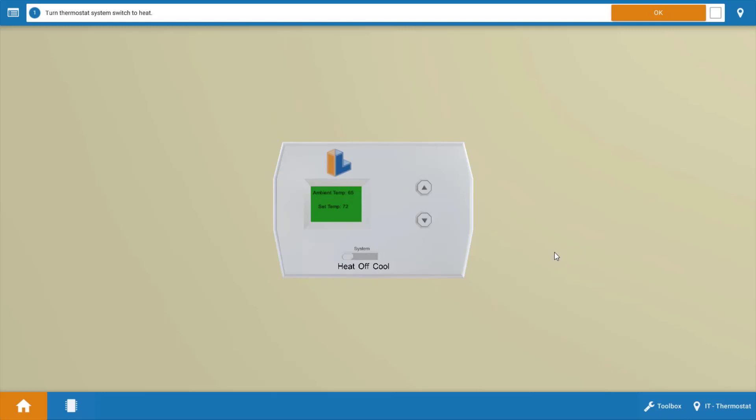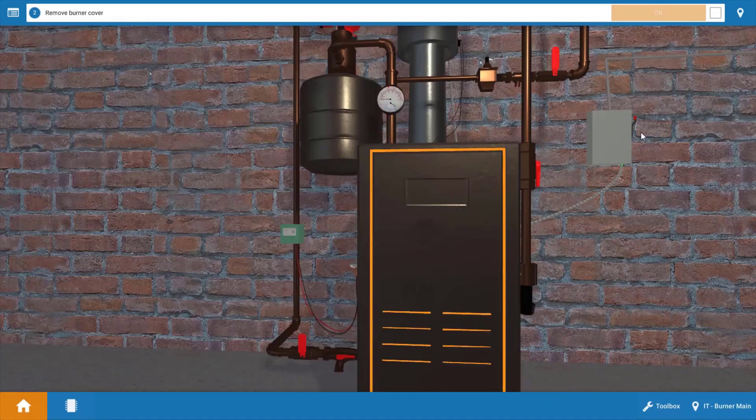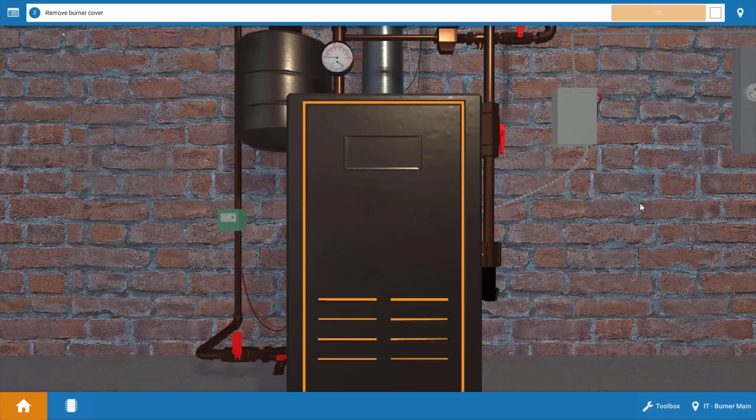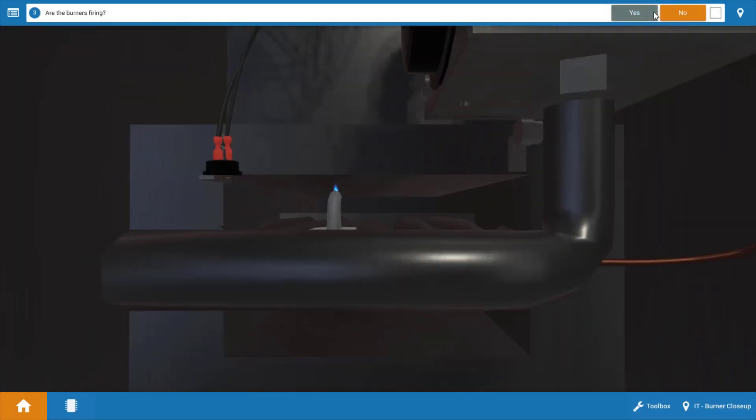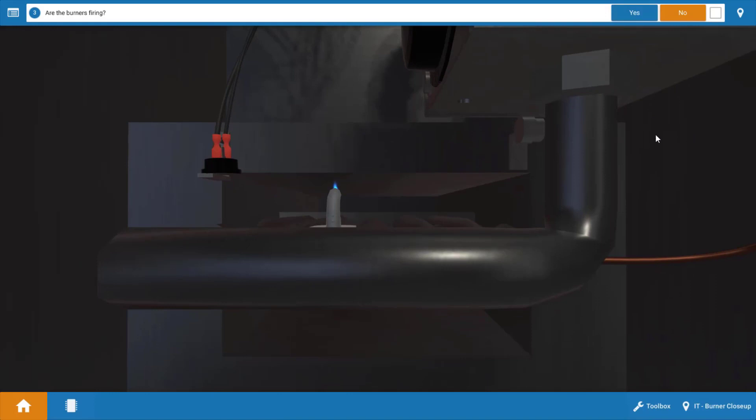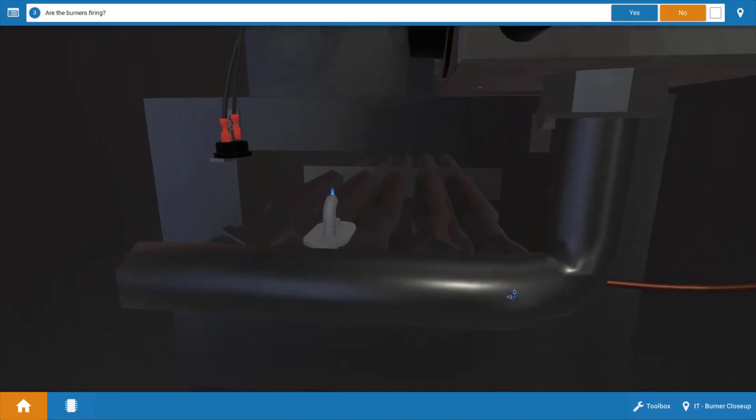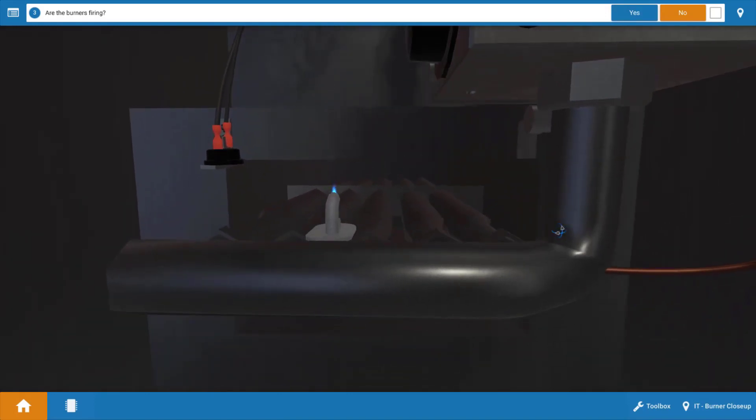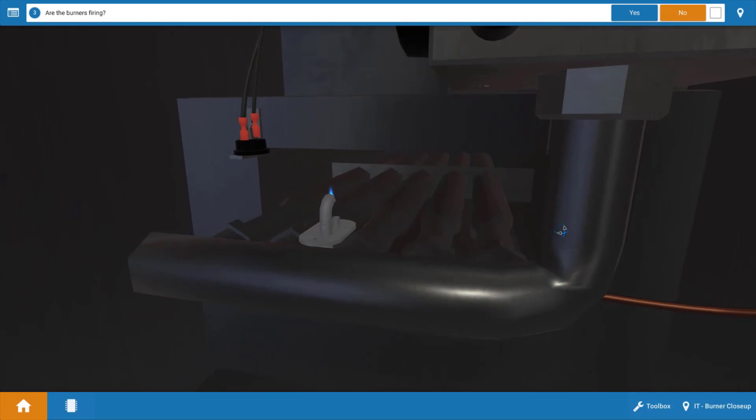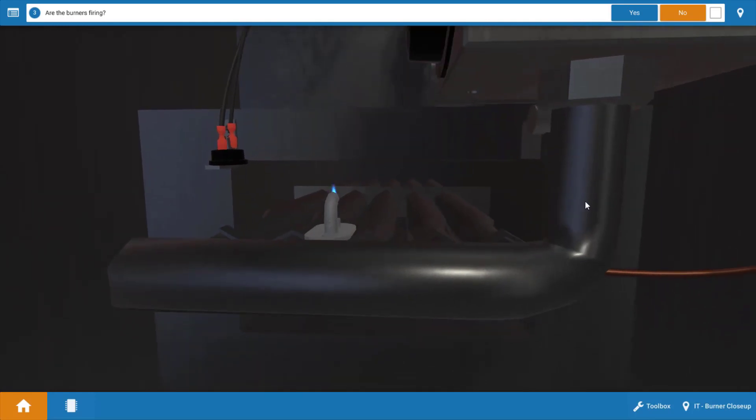Now remember after each step you're going to have to refer to the procedure guide at the top, so click okay. Next we're going to remove the cover from the boiler and now we're going to take an inventory of what's running. We can see that our burners are not firing here. We do have a pilot flame but no burner operation. So go to the procedure guide and click no, the burners are not firing.